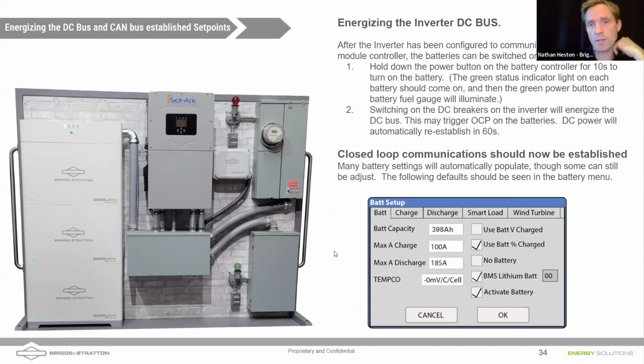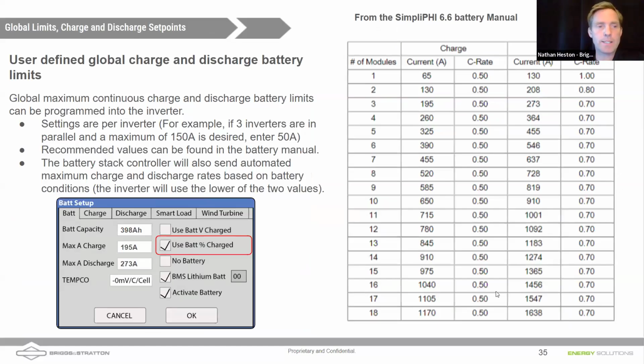So one of the first things, it's an important thing, is the first time you energize the DC bus, you're going to want to make sure that when you turn that inverter on, and I think it's a good idea to turn it on with battery power, grid power if it's available, you have to make sure you check this box for activate BMS lithium batteries. So that BMS lithium battery 00 box should be checked. And if that's checked, the inverter knows that it should be communicating on a CAN bus channel with the battery. Doing so should get you some automatic settings.